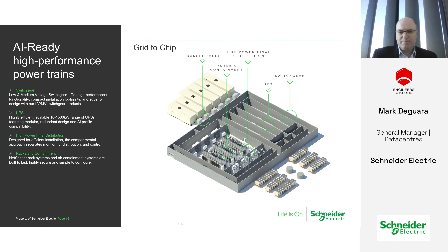If you look at this picture, you'll see the data center there, the grey space so to speak, and the infrastructure, generators, chillers, etc. on the outside. New AI data centers potentially have 25% less footprint for the white space, and if we go to 2 megawatts a rack, potentially even lower. However, the infrastructure to support it hasn't really changed. Traditionally, a lot of people put generators and chiller plant on the roof. Now if my data center has a smaller footprint, can I fit the generators and chillers on that roof anymore? If I have the weights we're talking about, does it limit the number of stories I have? Do I have 1 story? Do I have 2 stories? So it has a whole impact.